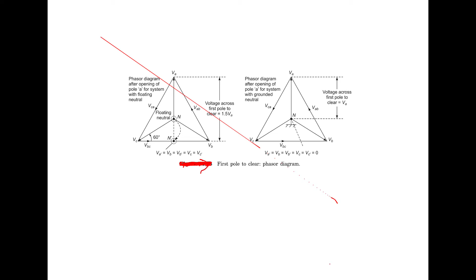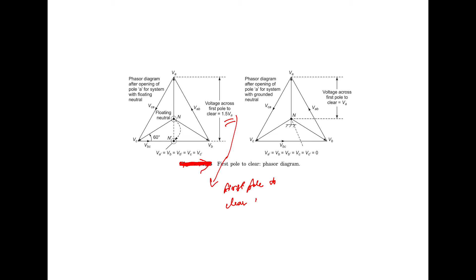So from this phasor diagram, you will see that the first pole to clear will be subjected to the recovery voltage of 1.5 times the line to neutral voltage. That is, VA is the line to neutral voltage. So the first pole to clear will be subjected to the recovery voltage of 1.5 times the line to neutral voltage.